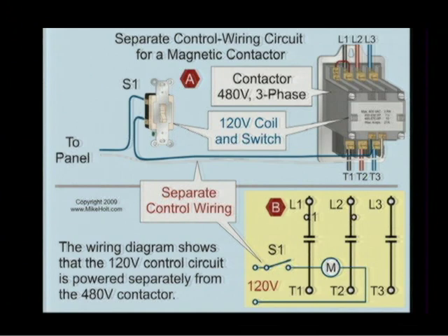That's true. Yes. It's become the industrial standard that when you're dealing with 120/208, you look at black, red, blue. When you go up to 480, typically it's going to be brown, orange, yellow. All right. So let's go on. We'll go ahead and get brown, orange, yellow colored on all our 480 volt graphics that we're working from.